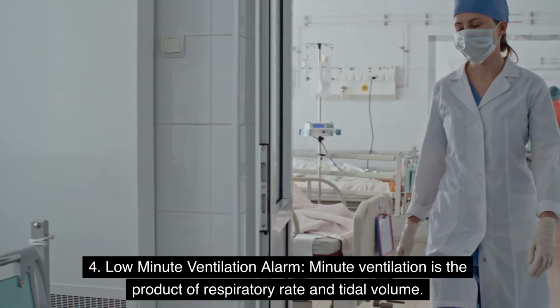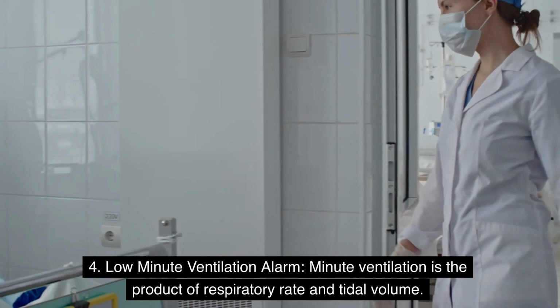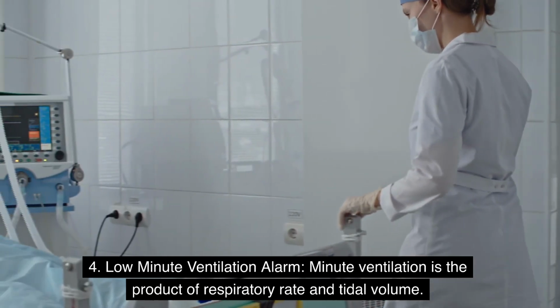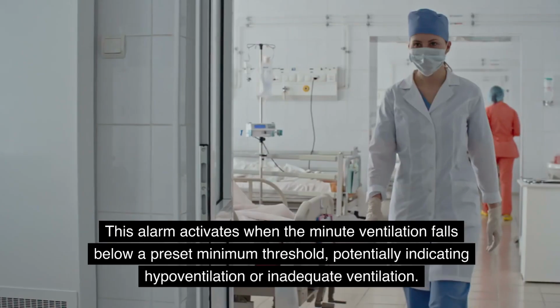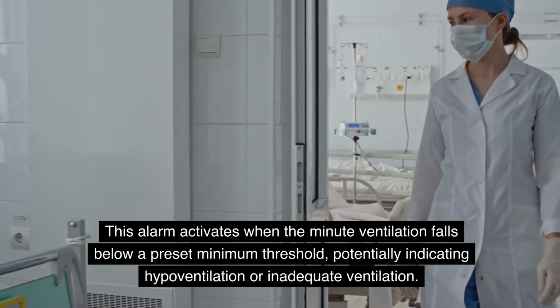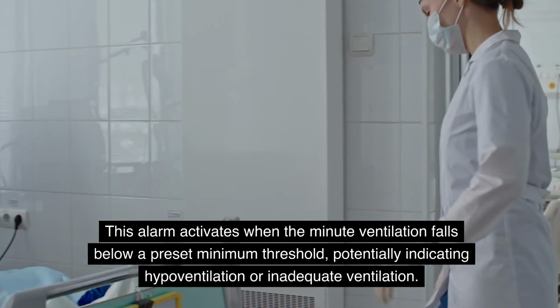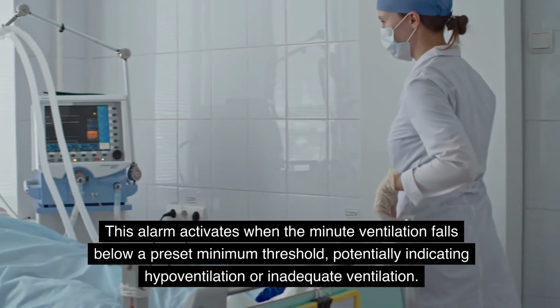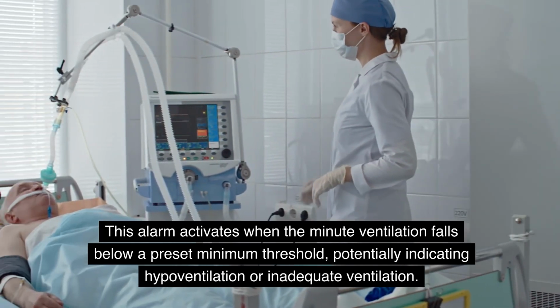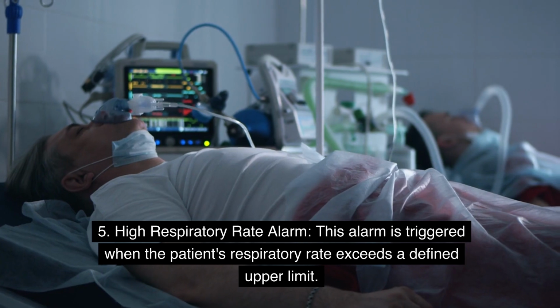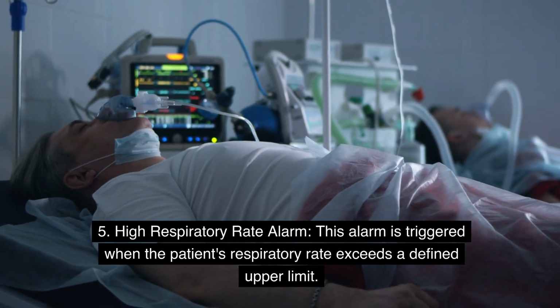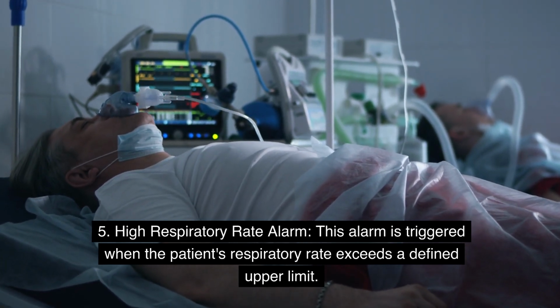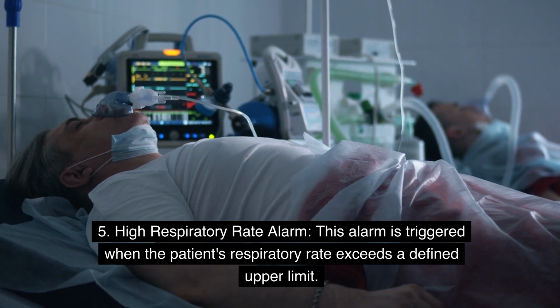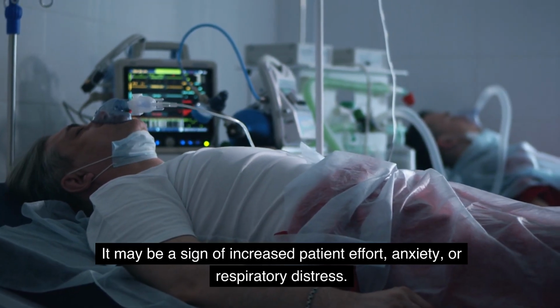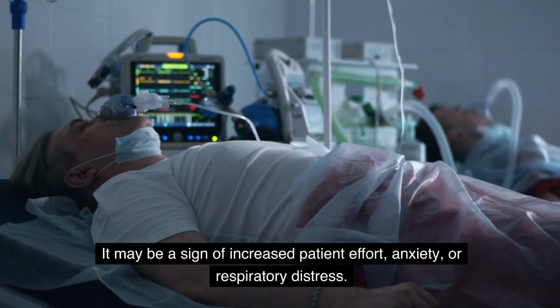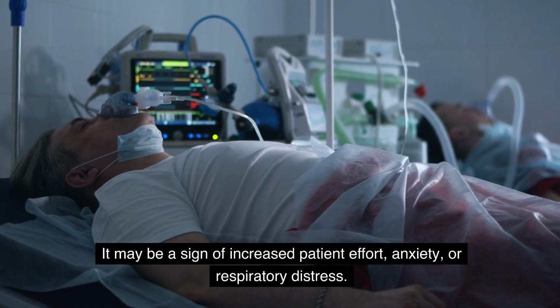4. Low minute ventilation alarm. Minute ventilation is the product of respiratory rate and tidal volume. This alarm activates when the minute ventilation falls below a preset minimum threshold, potentially indicating hypoventilation or inadequate ventilation. 5. High respiratory rate alarm. This alarm is triggered when the patient's respiratory rate exceeds a defined upper limit. It may be a sign of increased patient effort, anxiety, or respiratory distress.